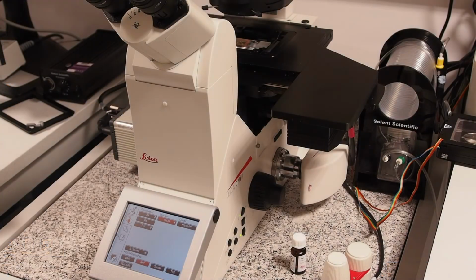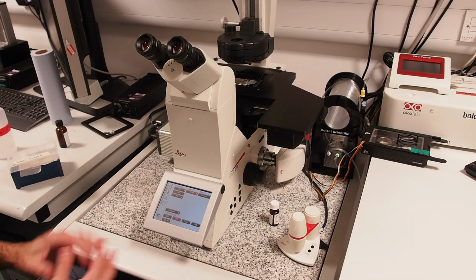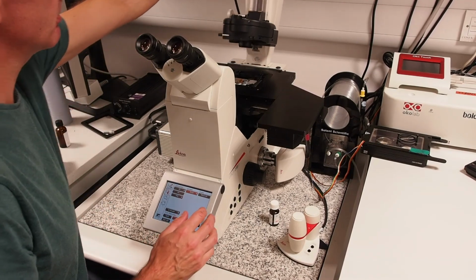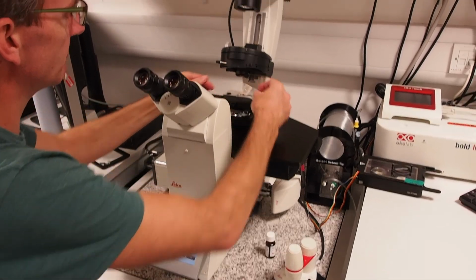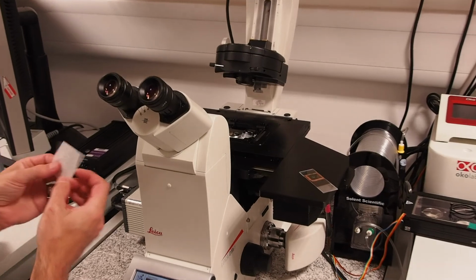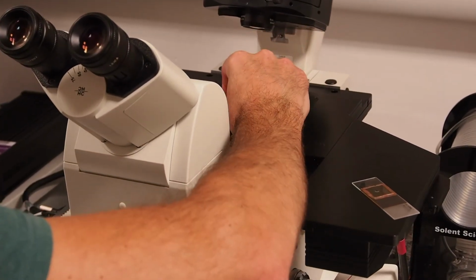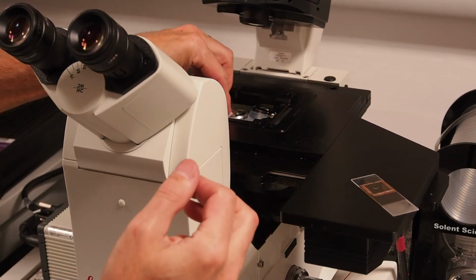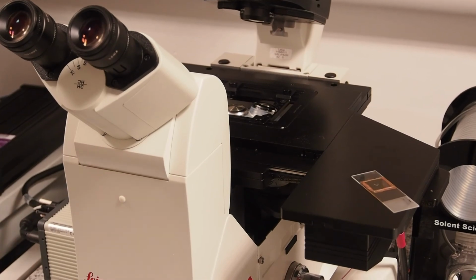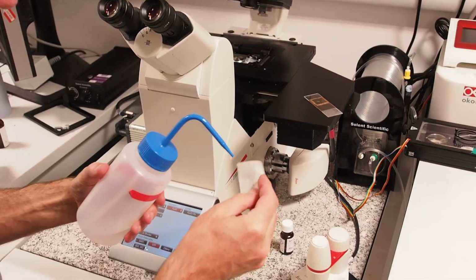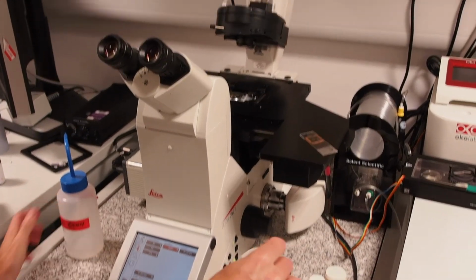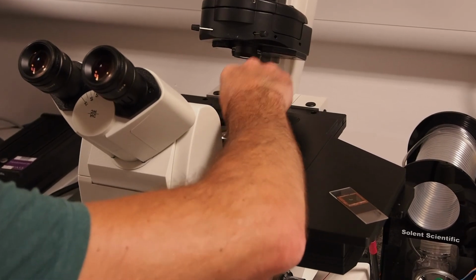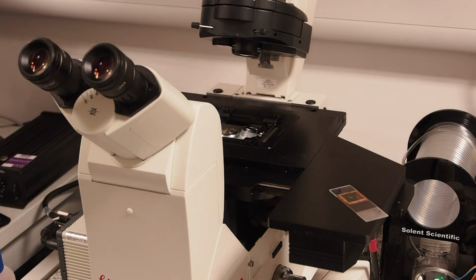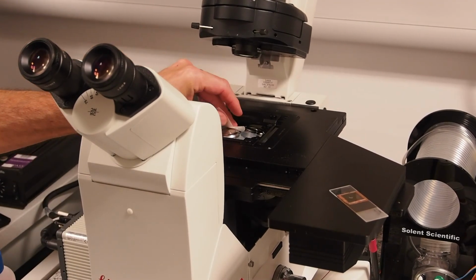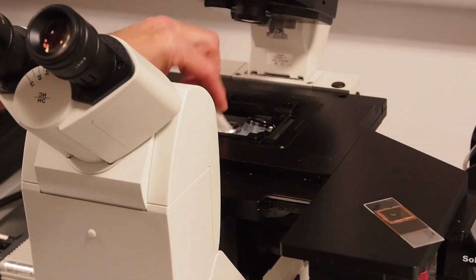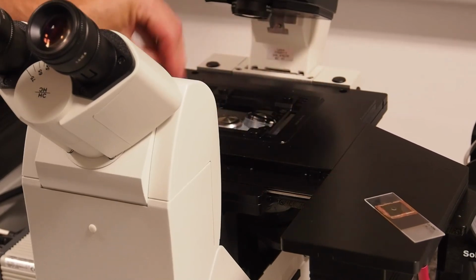Now we'll go over the hardware shutdown. Once you have finished your imaging, tilt the condenser arm back and remove your sample from the stage. Take a piece of lens tissue and carefully wipe any oil from the lens surface and barrel. Take a second piece of lens tissue, moisten with ethanol before wiping away any oil residue from the lens. Lastly, take a final piece of lens tissue to wipe off any residual alcohol from the lens surface. Remove any oil from the stage and discard the lens tissue in the bin provided.